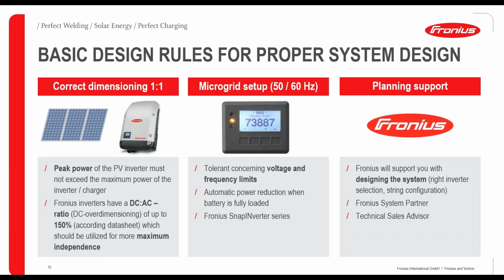To guarantee success, you must keep in mind these 3 design rules. First, the correct dimensioning, meaning the 1-to-1 dimensioning: the peak power of our PV inverter must not exceed the maximum power of the inverter charger.